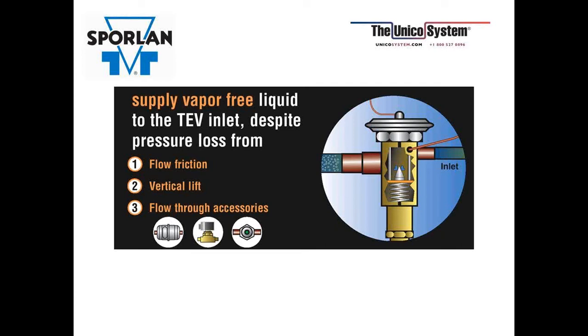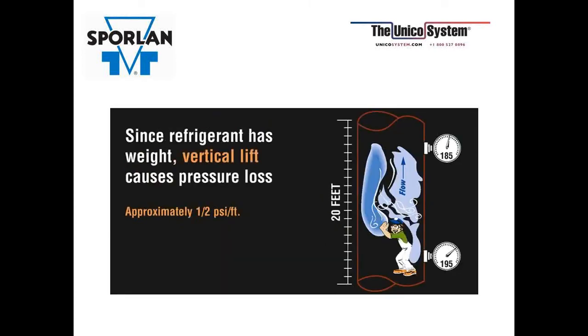And one point to remember on line sizing: if in doubt, use the next size up. But in this case, make sure you follow Unico's line sizing suggestions to reduce the flow friction mentioned in point 1, because they do the work for you. Since refrigerant has weight to it, any kind of vertical lift will cause pressure drop. And so if you're taking this up to the attic, you're going to have 20 foot of lift at least. So approximately half a PSI per foot for most common refrigerants.